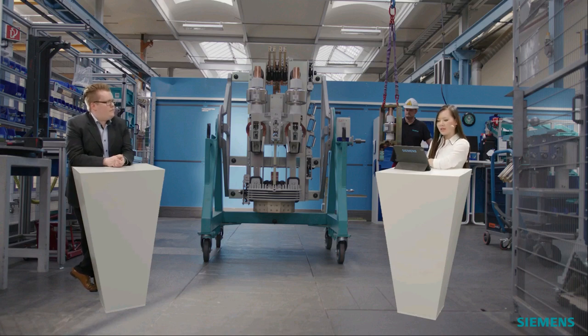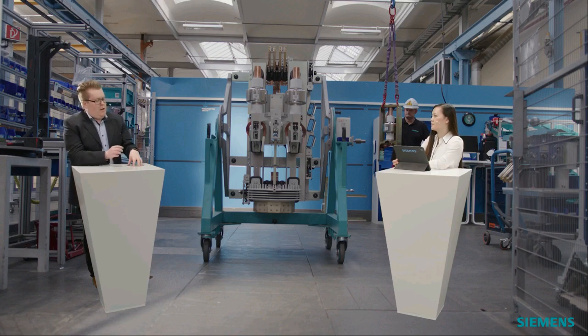Is it able to check the DC components also in the estimation tool? Unfortunately, this is not possible because to check the DC percentage, we have to know the detailed generator data, because the DC percentage is calculated due to the transient behavior of the short circuit current. And as I've said, the transient behavior cannot be covered by the estimation tool. That's why if you contact us with the generator data, we can easily calculate the DC percentage and present it to you.